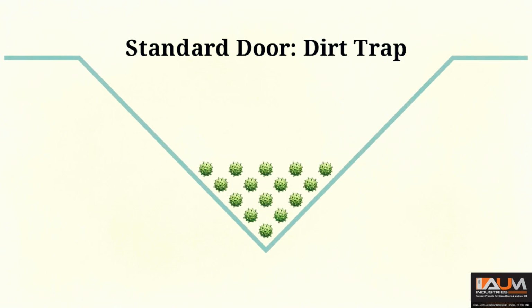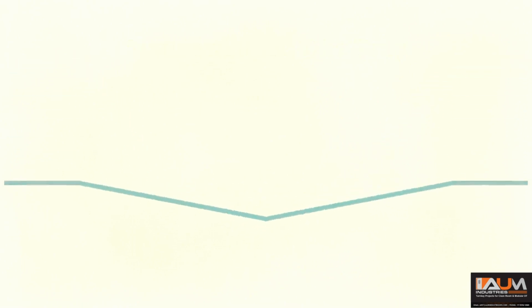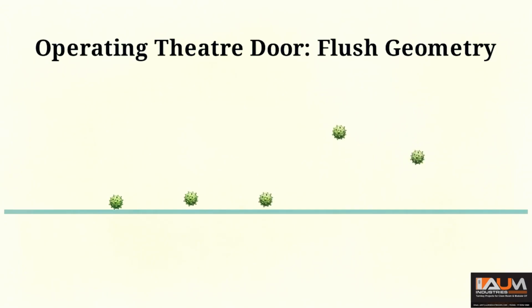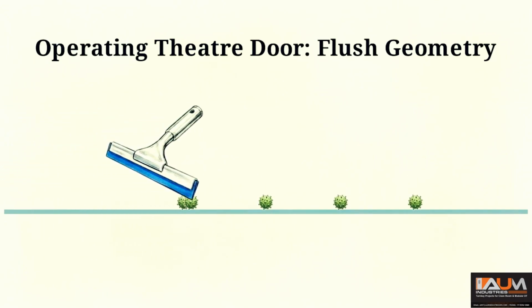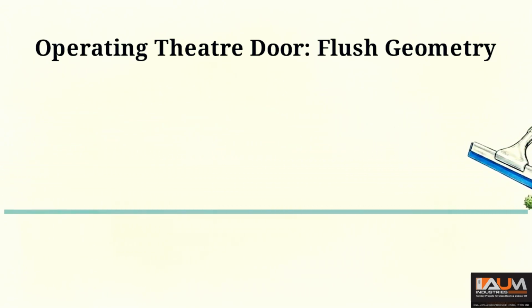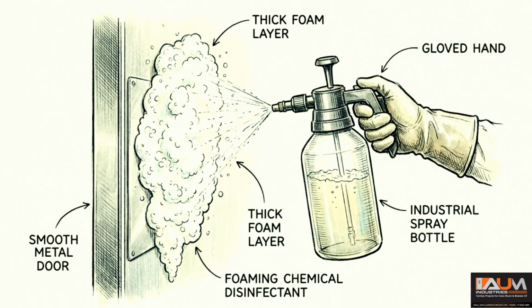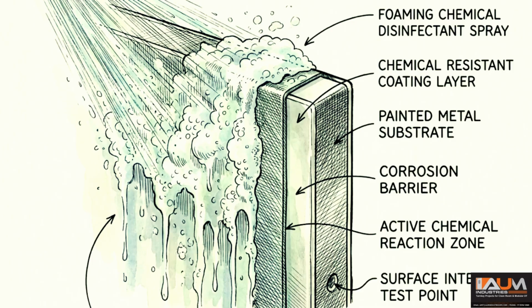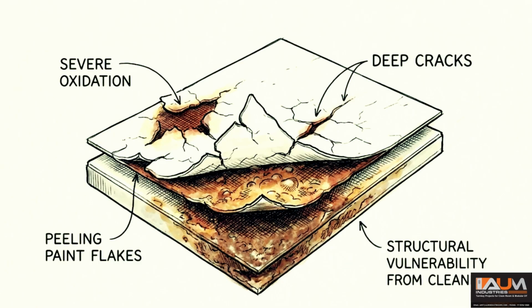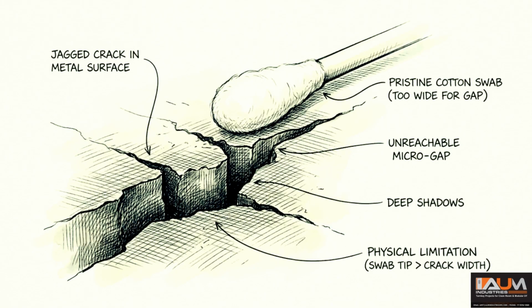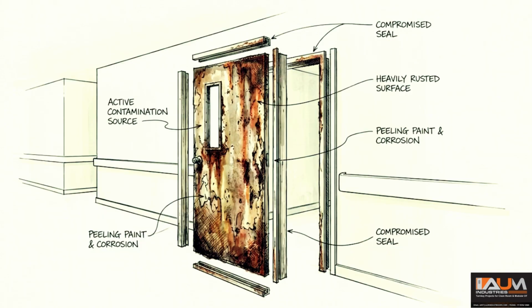A proper operating theater door uses flush geometry and seamless edges. There are no exposed joints. When the cleaning staff sprays down the surface, it can be wiped completely clean in a single pass because the dirt traps have been entirely engineered out of existence. These doors also have to survive heavy, repetitive chemical disinfection protocols every single day. If the material isn't high-grade stainless steel or heavily coated galvanized metal, the strong cleaners will cause the surface to peel and crack. The moment a door surface cracks, it becomes impossible to fully sanitize. The barrier meant to protect the room turns into an active source of contamination.